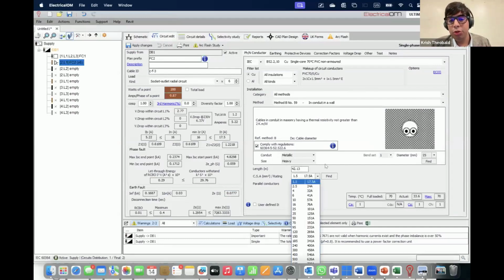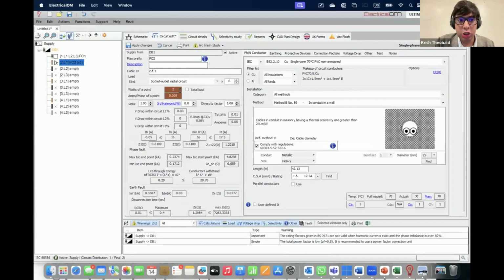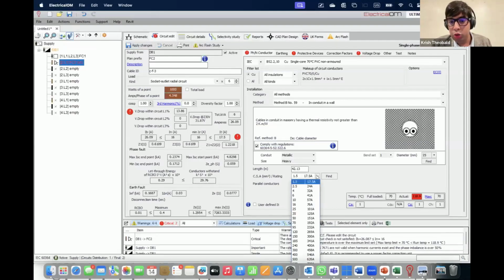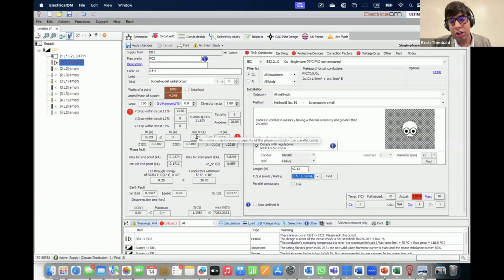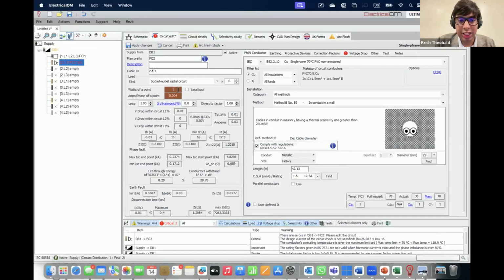Now, automatically it tells me what is the load required. Now, you see if I increase this to say 1000 watts, sorry, automatically it's now telling me that I have an issue. I can no longer use this. Firstly, my load current is exceeding the protective device rating. So say if this was 700, that's still an issue. Well, is it? Yeah, it's still an issue.